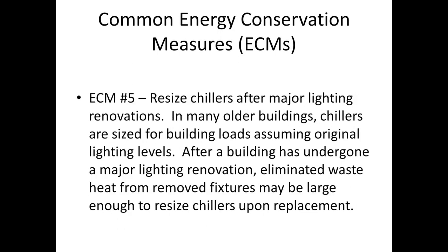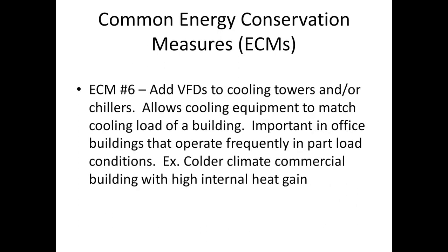We mentioned this before, but a lot of buildings, especially if they're 20, 30 years old, have chillers that are original to the building still. They're usually sized for the design load that was current at the time of the building, but a lot of changes and improvements in other technology allow us to reduce the size of a lot of this equipment. This goes for both heating and cooling equipment. Again, adding VFDs to cooling towers and or chillers: a lot of times adding VFDs to cooling towers can allow you to save. You increase fan energy, but reduce energy required by the chiller to actually provide chilled water.